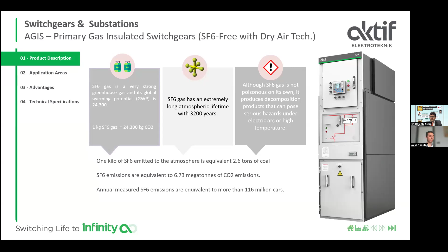If you are using SF6 gas in your facility, you will have obligations to report the F gases, special equipment to use, training people who operate the products, and maintenance problems due to use and fill and unfill of the SF6 gas. For all harmful effects of SF6, countries are publishing their own restriction plans. The first important regulation from the EU: 24 kilovolt and lower voltage level switchgears will be banned after 2026. Upper voltage levels than 24 kilovolts, like 36 kilovolt, will be banned after 2030 in the EU.